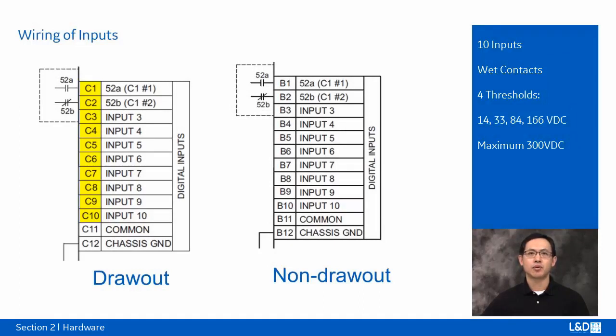C1 to C10 are for drawout type and B1 to B10 are for the non-drawout type. These contacts are wet contacts, and the inputs should be connected to the positive terminal of an external DC power supply. The negative side of the external source must be connected to the relay's DC negative rail at terminal C11 for DC drawout type and B11 for non-drawout type. The inputs can be programmed to different thresholds depending on the DC voltages. There are 4 threshold levels: 14 volts, 33 volts, 84 volts, and 166 volts DC. The maximum external source voltage for this arrangement is 300 volts DC.